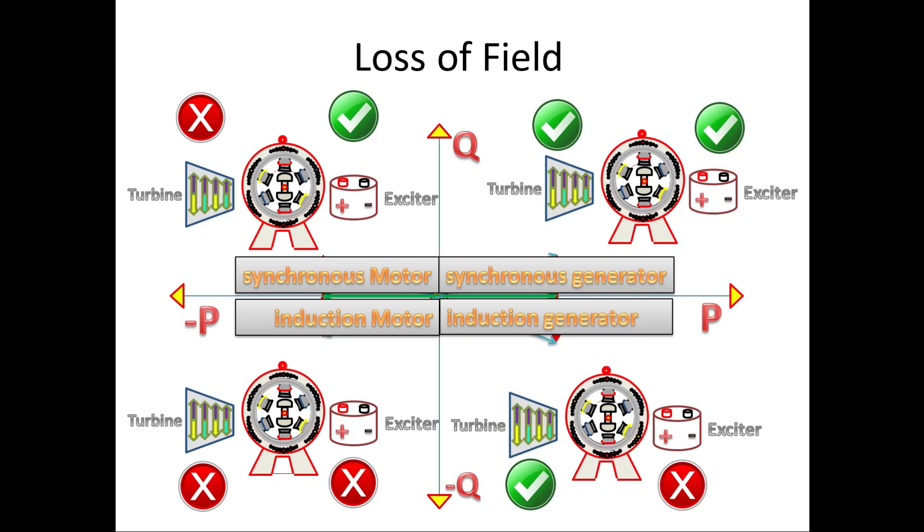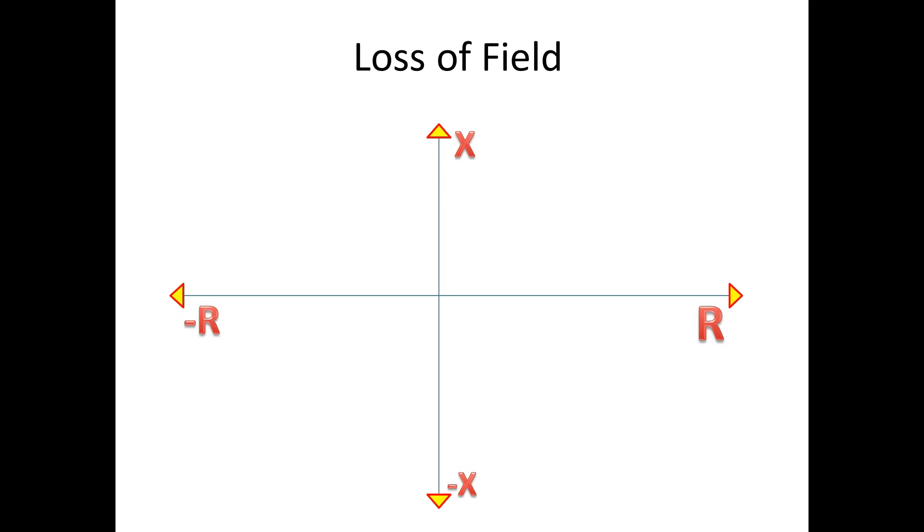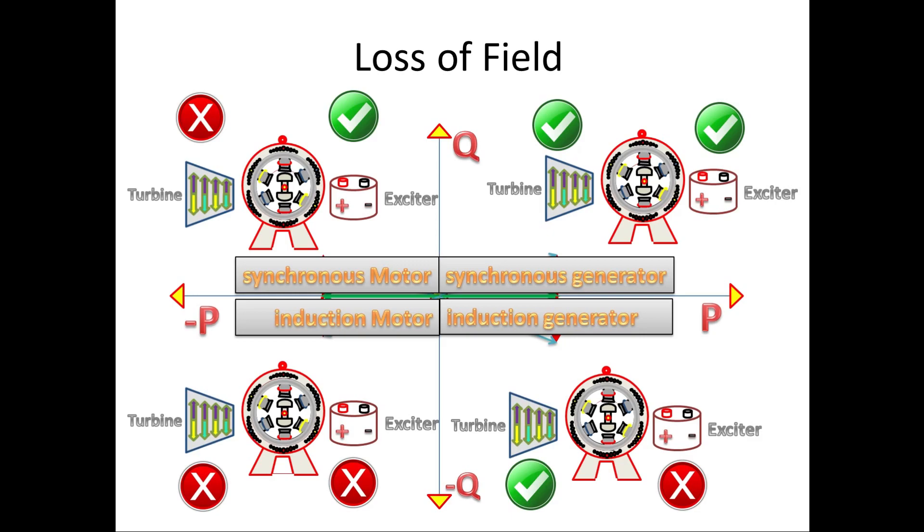From this we all can understand that the synchronous generator can run or modify into any quadrant, that is any mode of operation. But this synchronous generator is designed only for synchronous operation. That is it has to operate in first quadrant. If it operates in other quadrant due to failures of turbine control or exciter problem, then it is danger for system and generator.